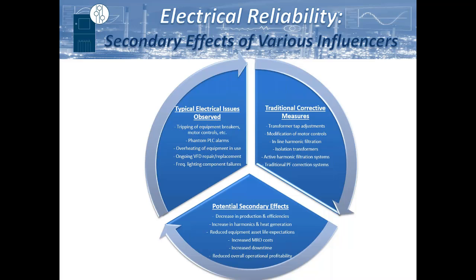And there's a myriad of different corrective measures that can be put in place. Oftentimes you might see a facility adjust their transformer tap settings to increase their nominal voltage to ensure that whenever they have a large motor start, it doesn't drop that voltage level to such a degree that it would impact other equipment on the network. Also, oftentimes they may put in some limiting factors within the PLC controls so as not to create a condition which could trip things out. And you also have other solutions like inline harmonic filtration, isolation transformers, active harmonic filtration, and even traditional power factor correction solutions as well. But each of these has secondary impacts that all need to be taken into consideration.